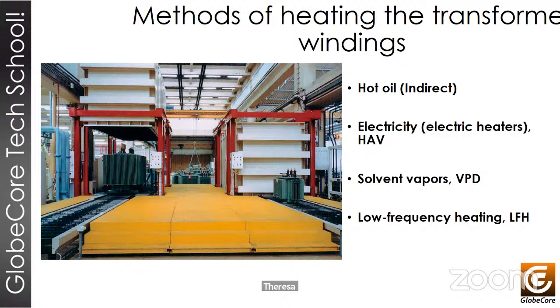The next method of heating is with solvent vapors. It is a completely different and more complicated method of drying the insulation. Transfer of heat to the winding is facilitated by spraying a heated solvent in the chamber, and this heated solvent serves as a heat carrier. Moreover, when repairing used windings in the course of drying, the hot solvent displaces old oil from the winding. This method is good, but the complexity of maintenance and production affects its expediency. The same goes for operation with the use of explosive hydrocarbons.